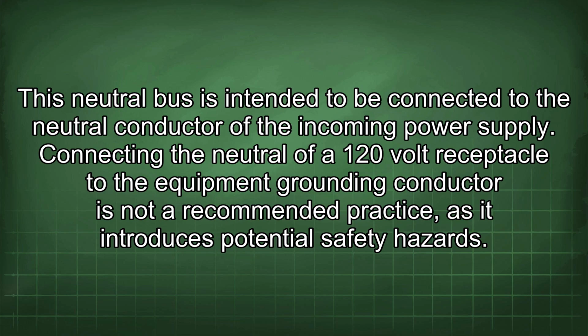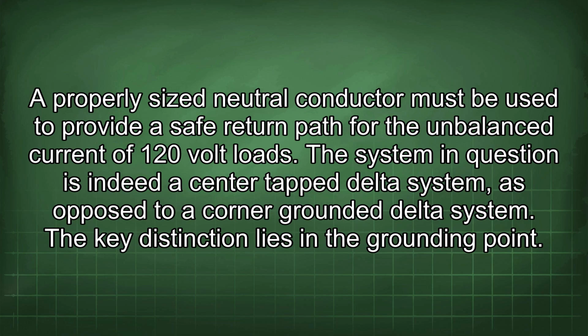Connecting the neutral of a 120 volt receptacle to the equipment grounding conductor is not a recommended practice, as it introduces potential safety hazards. A properly sized neutral conductor must be used to provide a safe return path for the unbalanced current of 120 volt loads.